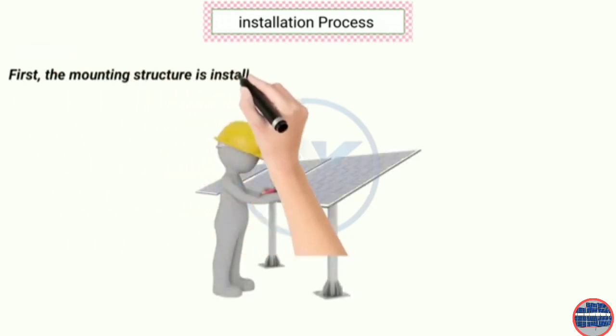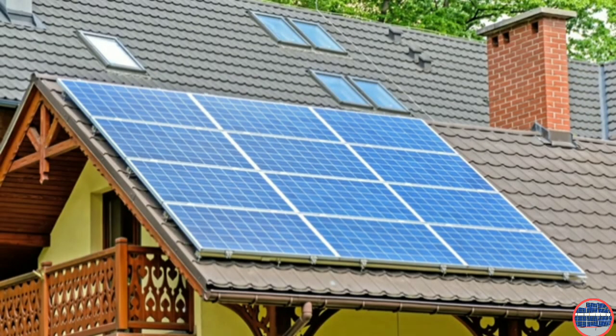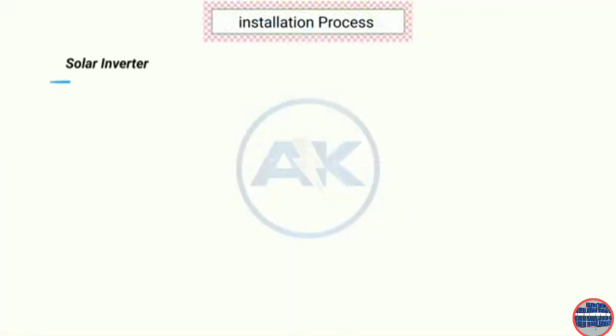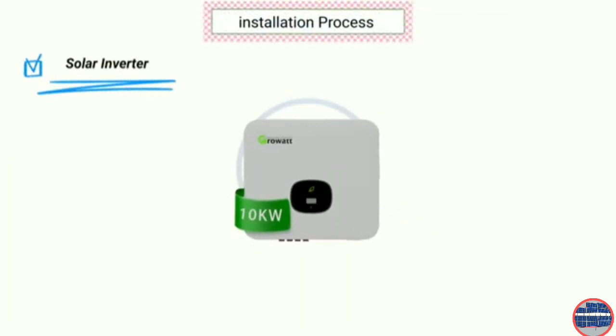Now let's get into the installation process. Section 1. Panel installation and string sizing connections. First, the mounting structure is installed, ensuring it's securely attached and aligned correctly. Then the solar panels are mounted onto the structure. Solar inverter. The Growatt 10 kW on-grid inverter is a popular choice for residential and commercial solar installations due to its high efficiency, reliability, and competitive price.